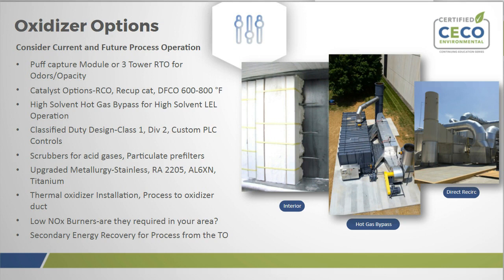And then finally, we do have secondary energy recovery for the RTO, because the RTO is so energy efficient. A lot of times there's just not much you can get out of the exhaust of an RTO because it's kind of been cooled down by the internal system of it. But on other thermal oxidizers, it's definitely been used a lot. So I'm going to hand it back over to Brian just for a second here to talk about secondary heat recovery options.